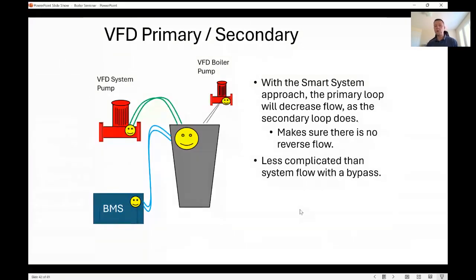Okay, we'll alter our algorithm. We'll make sure we don't change the set point. We'll also take a look and maybe ramp that VFD pump down if we're going to get into a situation where we have too much flow in that boiler loop compared to the system loop. So I like it because my boiler is in charge of everything. It's basically the BMS and everything telling it what to do, but not how to do it.